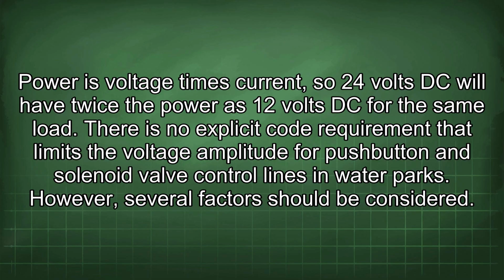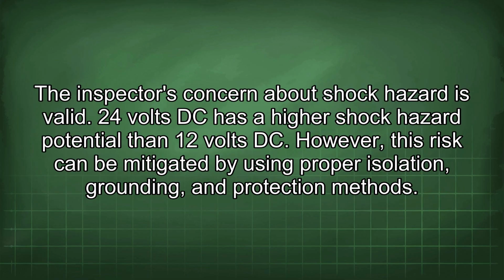There is no explicit code requirement that limits the voltage amplitude for push-button and solenoid valve control lines in water parks. However, several factors should be considered. The inspector's concern about shock hazard is valid. 24 volts DC has a higher shock hazard potential than 12 volts DC. However, this risk can be mitigated by using proper isolation, grounding, and protection methods.